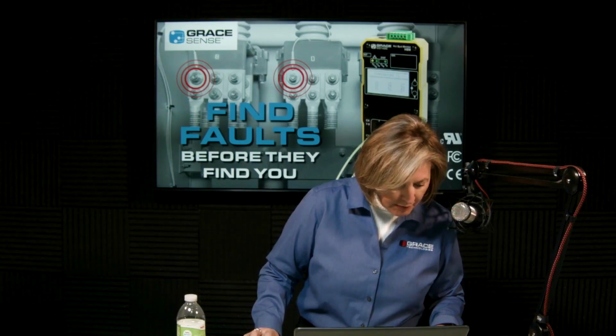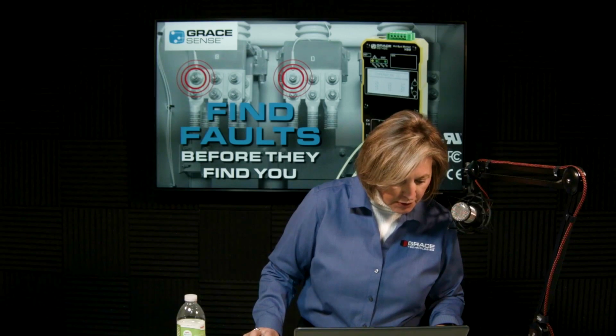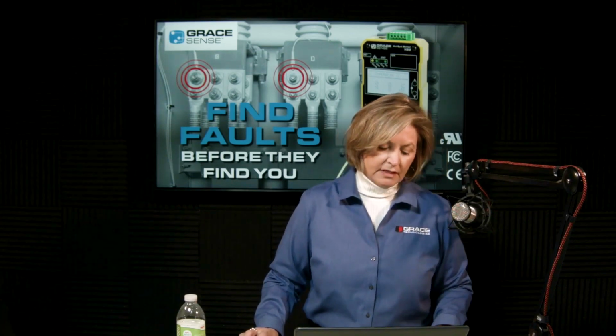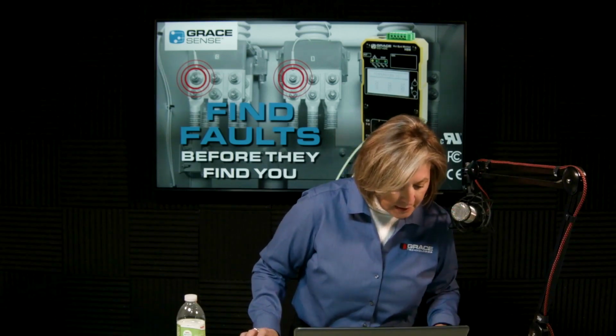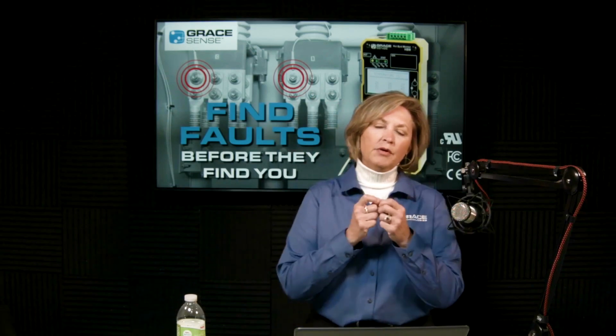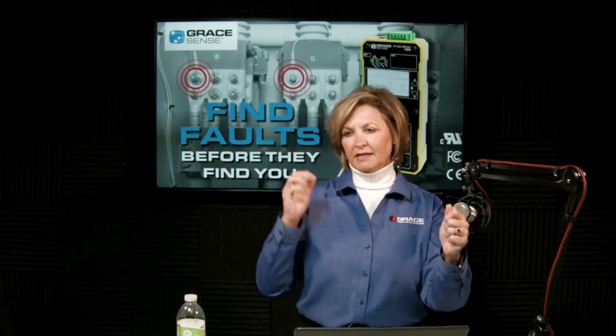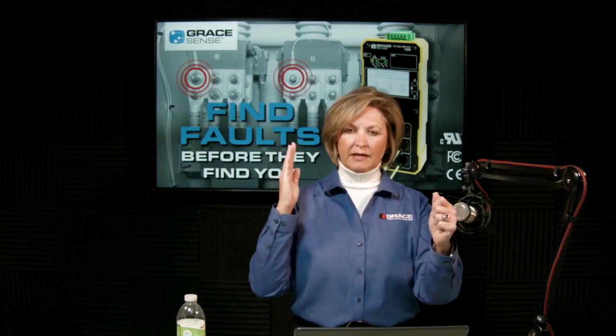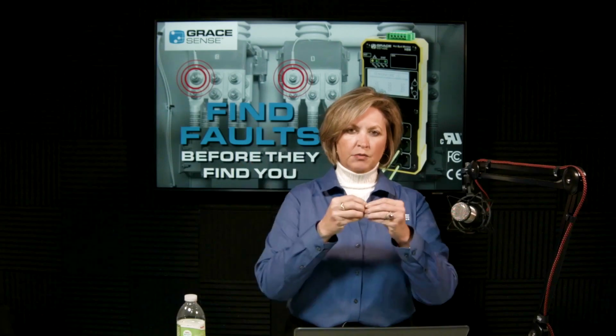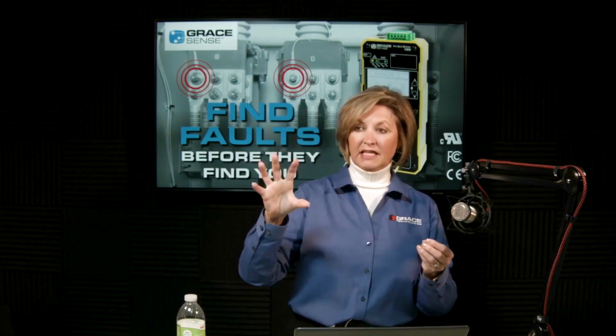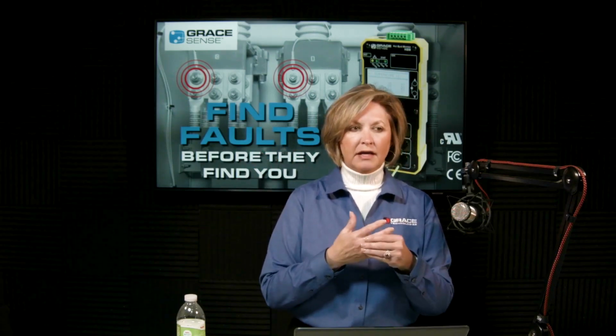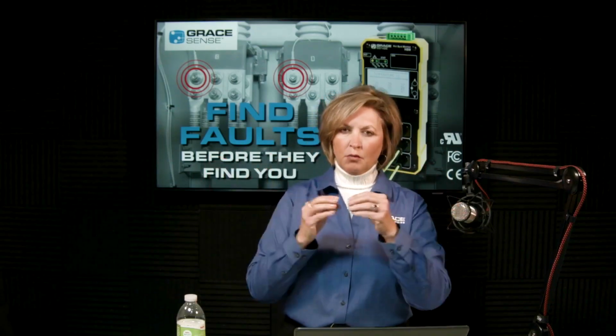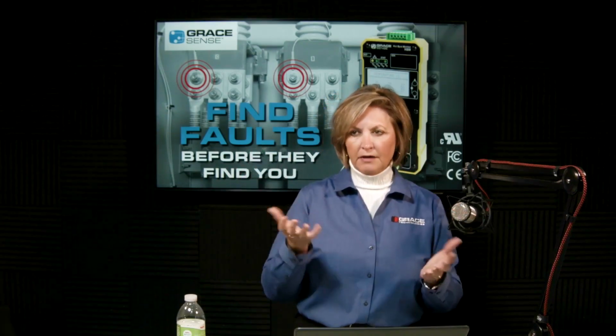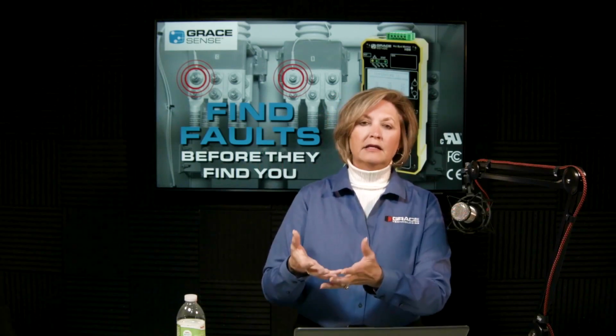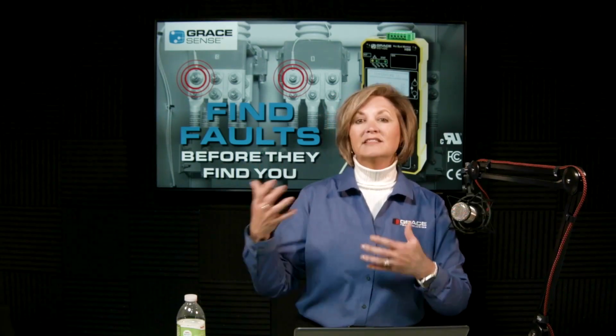Is there a median point where fiber optics could be spliced and reconnected in the future to a main electronic unit? So the reason that cannot happen, Hamid, is because the probe tip is expecting a certain time and wavelength, light wavelength, from the HSM. So the splicing, you could certainly coil it and leave it, but splicing of fiber is not something that is allowed with this product. It is specifically calibrated from the module to the tip. So we don't want any splicing going on, but certainly if you got a 15-meter fiber, you could coil that and leave it for the future installation of the fiber.